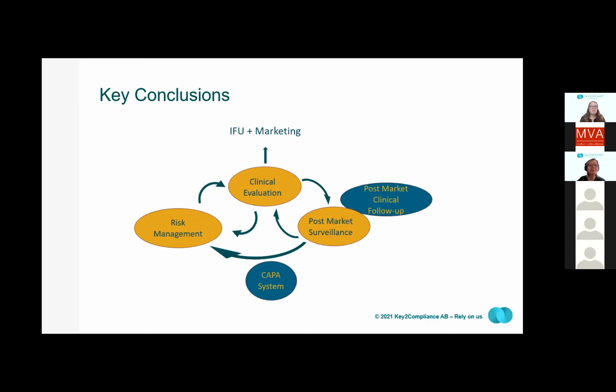Except for these interconnections, you will also find connections when you look at all requirements that are listed in the GSPR checklist, and you need to make sure that you have evidence of fulfillment of those requirements in your verification and validation section. So your verification and validation section should include both evidence for conformity with the standards and methods in order to fulfill the GSPRs, and also conformity with your own requirements specified in your different requirement specification.